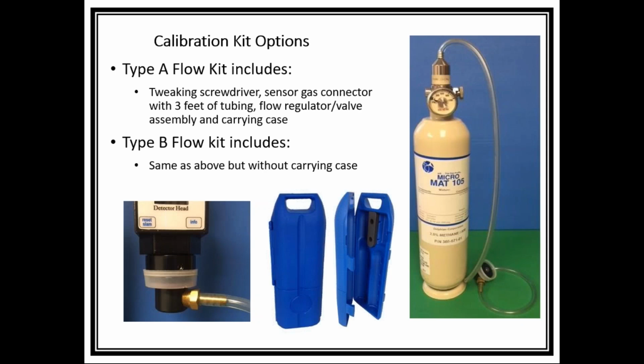So now we're into calibration kits. We have several different calibration kits that are available for specific gases or types of technologies that we use. The most common calibration kit is the Type A flow kit, which is basically a cylinder of gas, usually 105 liters, and that will allow, using a regulator, for you to flow gas at 1 liter per minute over your sensor. Now, this is typical in applications where your gases are not dangerous to the user.